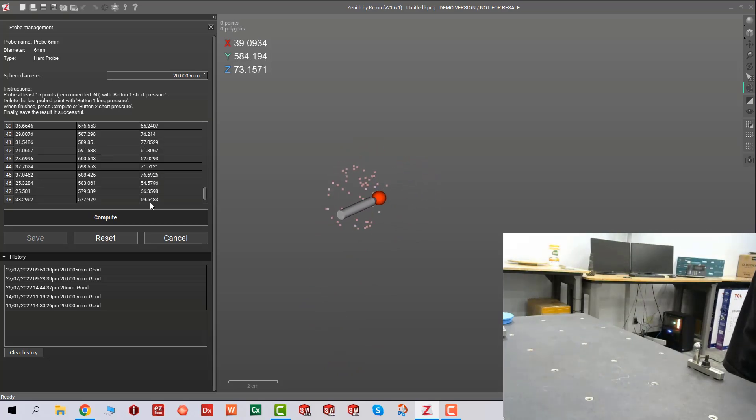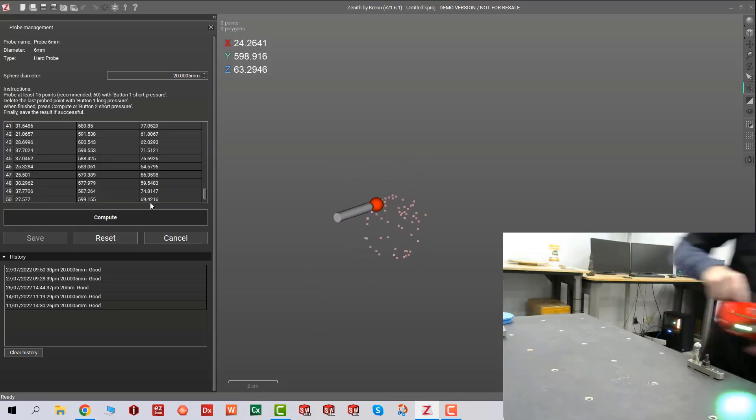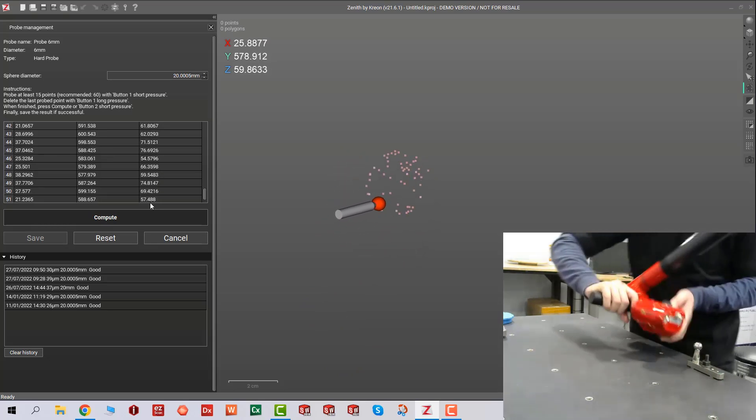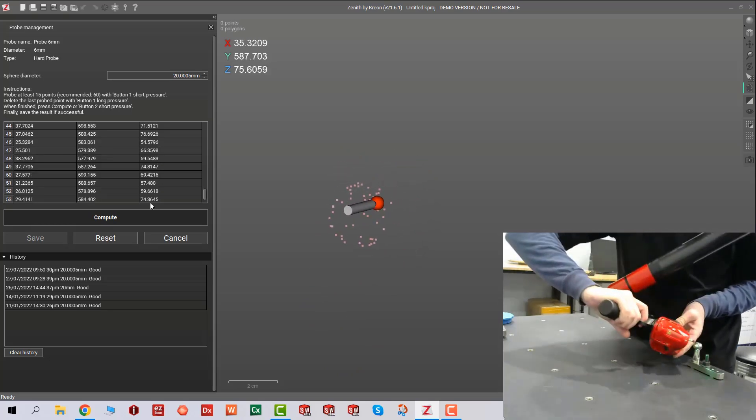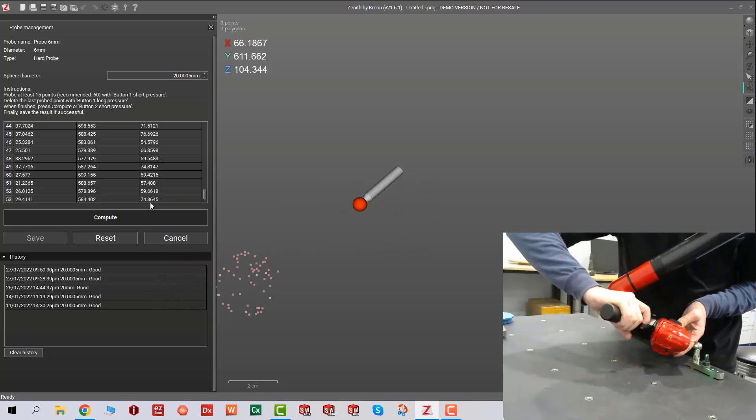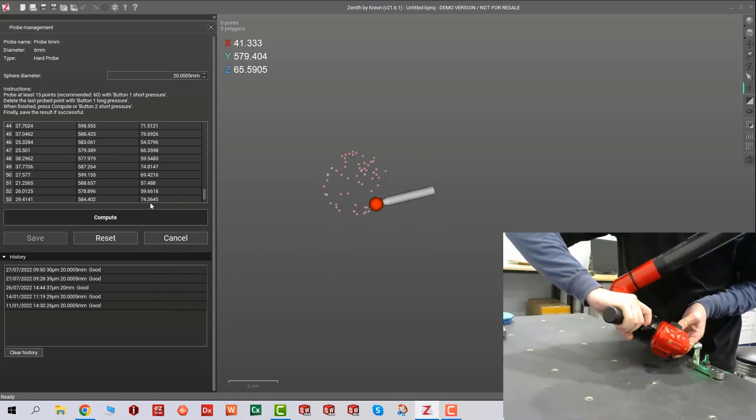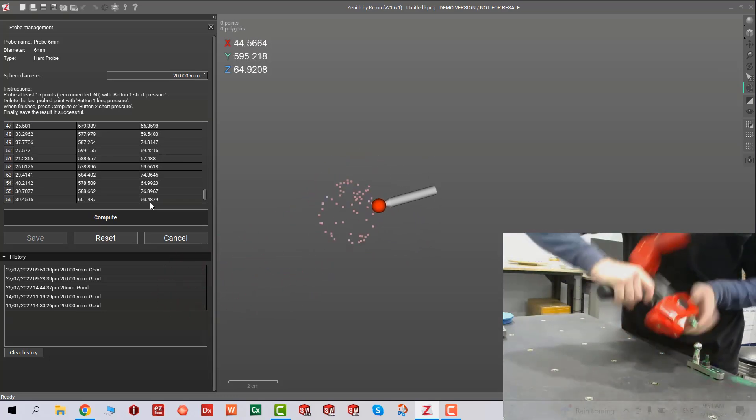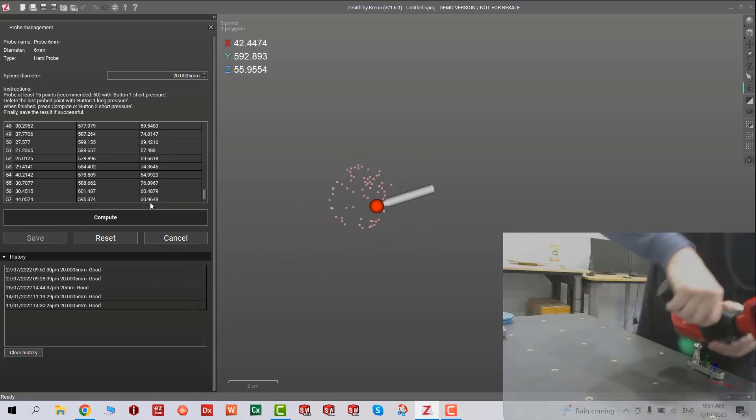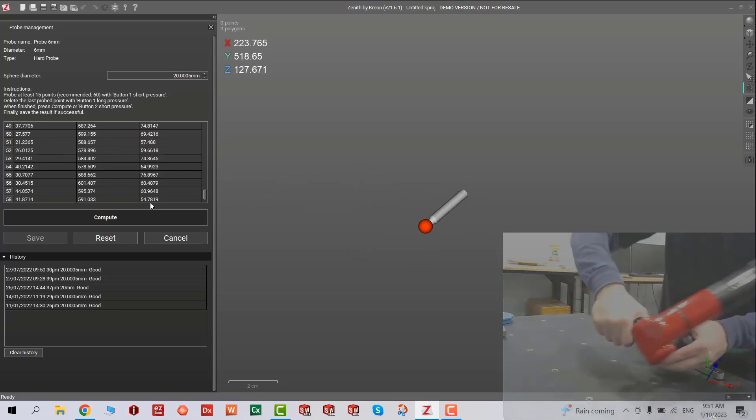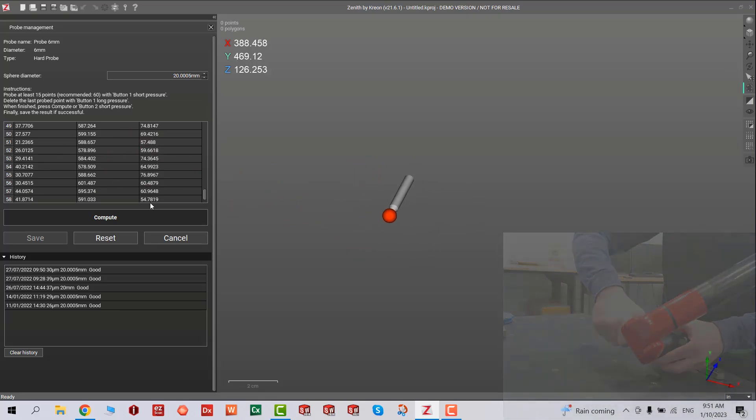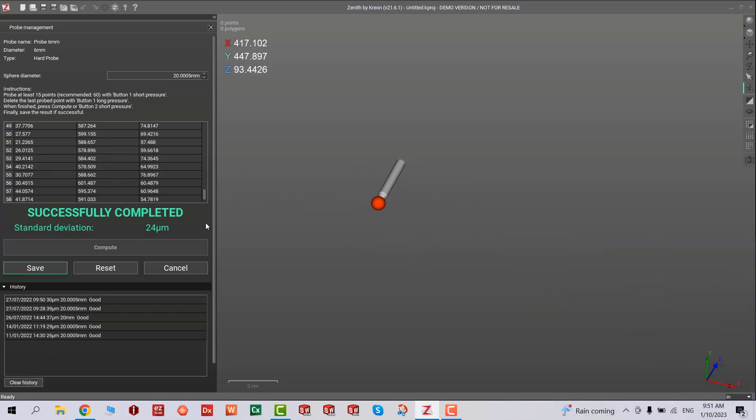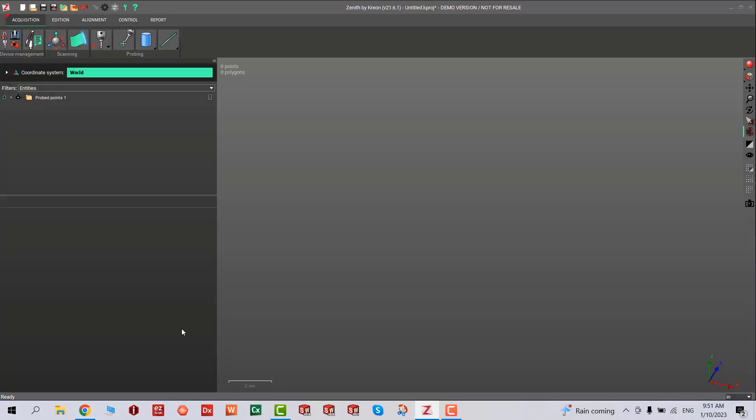Once you've completed 60 plus calibration points, click on compute. This will tell you how close you are for the calibration. 20 to 25 microns is really good for the probe. We got 24 microns, so we'll save it and start scanning.